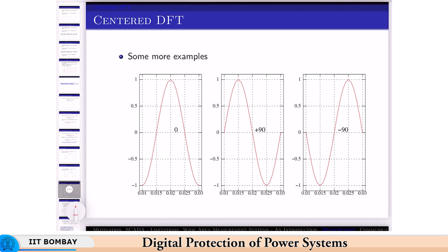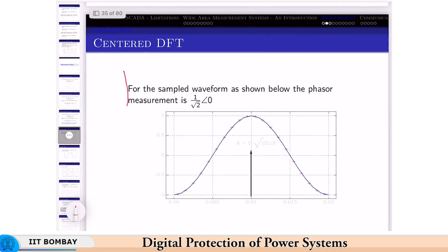Okay. So, while we discuss this as DFT and centered DFT, the standard does not specify the method of calculation of the phasor. You can use any method, 4 sample method, whatever you feel is the right method. What it does specify is total vector error. Okay. So, the error is specified. The method of calculation is not specified. As long as you meet this error criteria, you are free to use any method that you want.